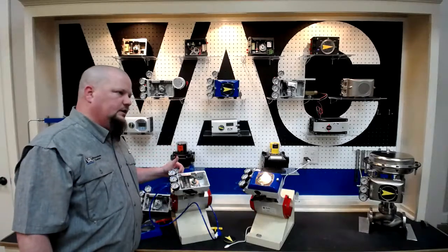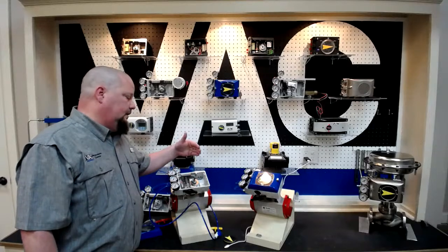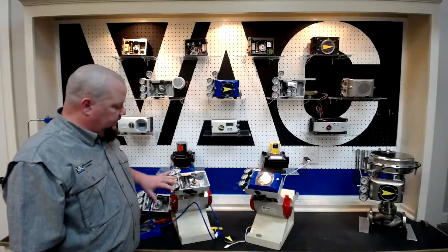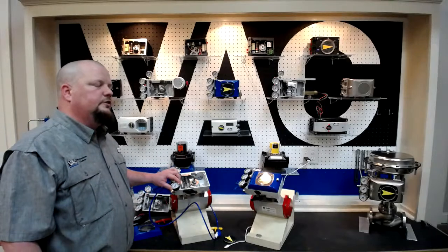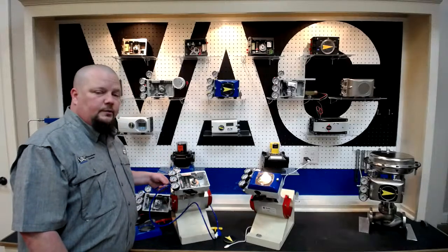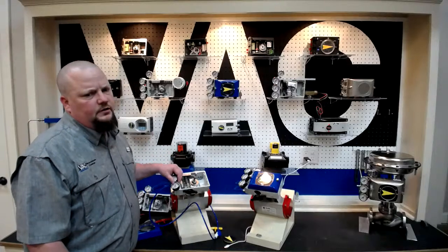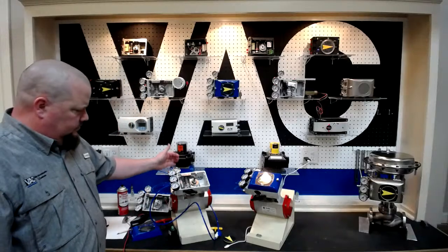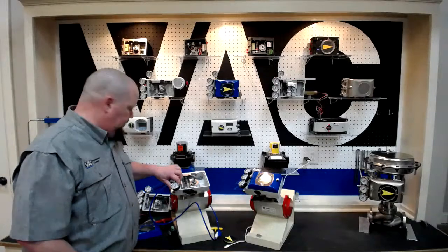But like I said, the important thing is that on this 3 to 15 gauge, at 4 milliamps you see 3 psi, and at 20 milliamps you see 15 psi. The other supply gauges will help you calibrate, and can help you determine if there's an issue inside the actuator, where if you're putting full pressure and you can't get it calibrated, you're showing bleed across. It could be leaking through on the actuator or something along those lines. But like I said, gauges are always going to be your friend when you're troubleshooting on these positioners specifically.